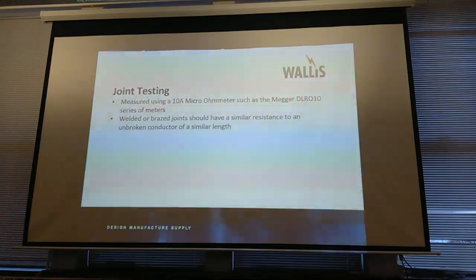Because we are dealing with quite long duration faults, 1-3 seconds, it's not like lightning protection. Lightning protection is the part of our business where we've got clamps, you get the tapes, they're not quite sitting right, but if you clamp them down, there's that much energy coming from the sky that a bit of an air gap between the copper tape isn't going to cause you that many problems. And it's over within microseconds anyway. When you're dealing with 1-3 second clearance times, there's a lot of energy, a lot of heating, so you've got to make sure that joint is sound.